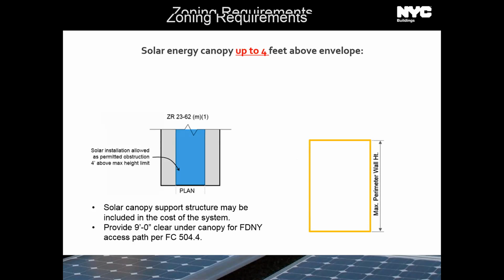If we take this rectangle, and this is the maximum permitted wall height, which is usually somewhere between 21 and 25 feet, you're usually allowed to go up to the maximum building height of 35 feet. The zoning resolution then allows you another 4 feet as a permitted obstruction. So what you do is you take that red dashed triangle and lift it up 4 feet, and there you can see you can easily put a canopy in there. The canopy should be 9 feet clear so that the fire department can have their required access. And in this particular case, the canopy structure can be included in the cost of the solar panels.